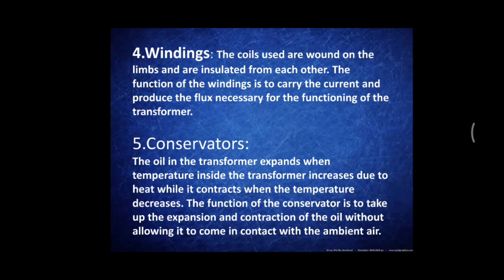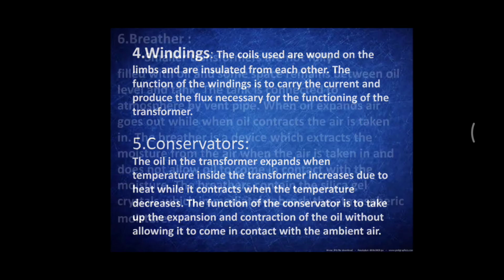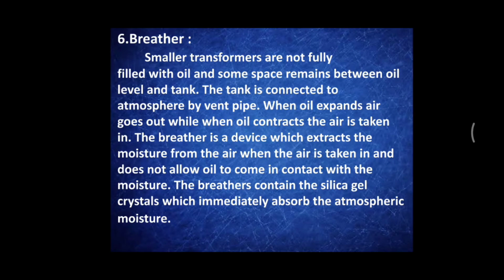The function of the conservator is to take up the expansion and contraction of the oil without allowing it to come in contact with the ambient air. Sixth is the breather. Smaller transformers are not fully filled with oil and some space remains between the oil level and the tank. The tank is connected to the atmosphere by a vent pipe. When oil expands, air goes out, while when oil contracts, air is taken in.